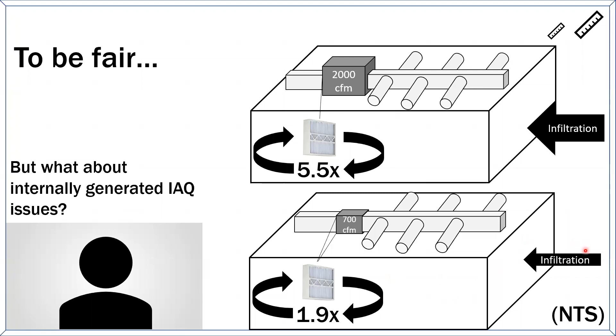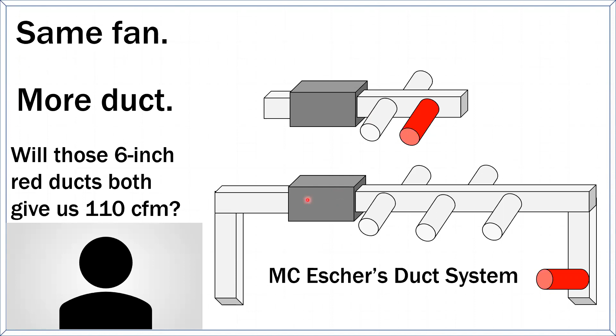So also, and this is one, that whole, we were talking about the watts per CFM thing. We're gonna have to keep an eye on that as an industry. We're starting to set unrealistic standards, right? Don't look too closely at this because it doesn't make physical sense. It's MC Escher's duct system, but shorter duct runs, my 3D drawing skills in PowerPoint are somewhat limited. But shorter duct runs for the same amount of air means it's easier to move that air. Longer duct runs means it's harder to move that air. That means all things being equal, that fan has to work harder, which means we are asking fans to be more efficient while they do more. That's not an easy thing to pull off. Okay. So, you know, you could make it a 7-inch and that'll be better, right? That's good.